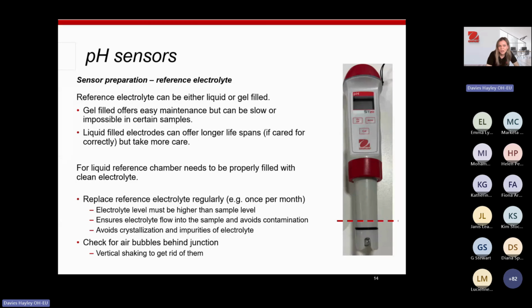For the liquid reference, the chamber needs to be properly filled with clean electrolyte. I'm not sure if you've got any users on today that have liquid filled reference electrodes, but if you do, you have to replace the electrolyte once a month. Again, don't top it up completely. Release everything that's in there, give it a rinse, and then replace it with fresh reference electrolyte regularly. The electrolyte level must be higher than the level of the sample. There is another picture on one of the slides which I'll show you. That ensures that the electrolyte flows into the sample and stops any contamination, and it avoids crystallization and impurities of the electrolyte as well. Also check for air bubbles behind the junction. A little bit of shaking side to side would generally get rid of any air bubbles in the reference.